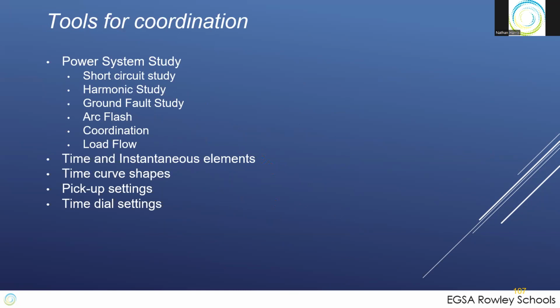To do these studies, we have a power system study. I wish I had more time to spend on this, but be careful with your power system study. It often gets forgotten. It's dependent upon every parameter you can think of: cable type, cable length, conduit type, connection type, impedance of the transformers, impedance of the generator. All this goes into figuring this power system study. Types of load, VFD, LED, have high harmonic content, all these things. And so everybody says, I can't do it. I don't have enough information. That often gets overlooked. So make sure you have this in the back of your mind.